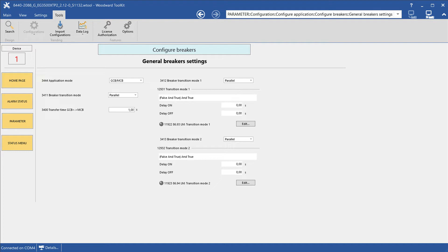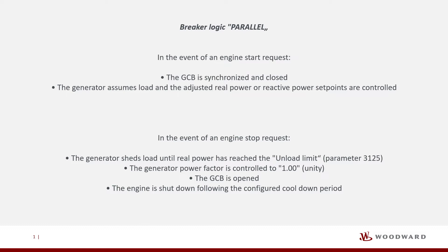Let's see how the breaker modes are working. Breaker logic parallel: in the event of an engine start request, the GCB is synchronized and closed. The generator assumes load and the adjusted real power or reactive power setpoints are controlled. In the event of an engine stop request, the generator sheds load until real power has reached the unload limit, parameter 3125. The generator power factor is controlled to 1.00 unity. The GCB is opened.